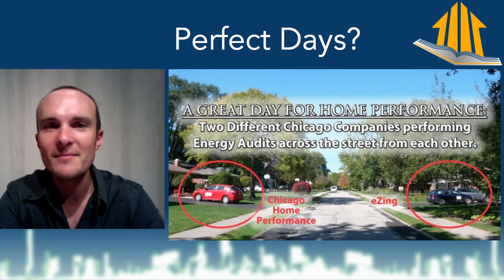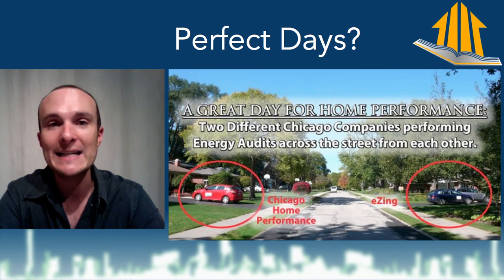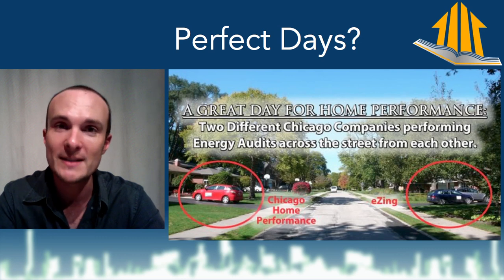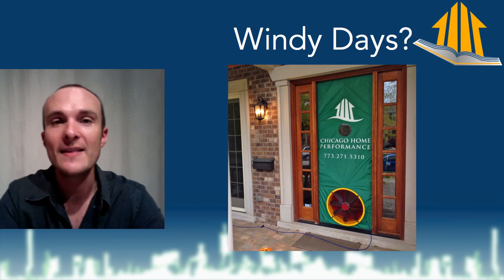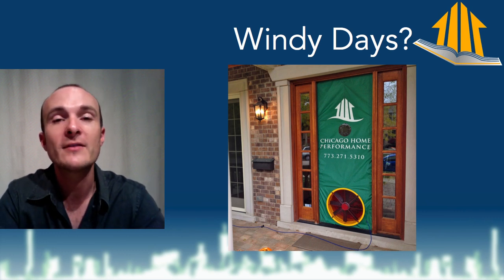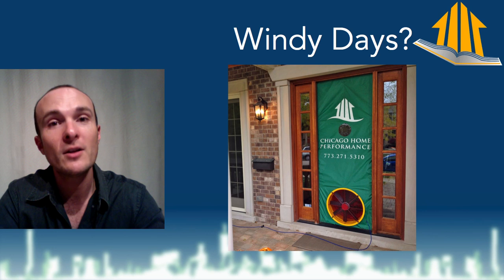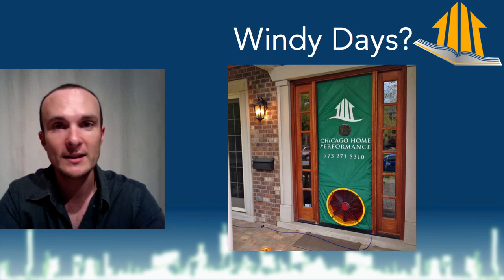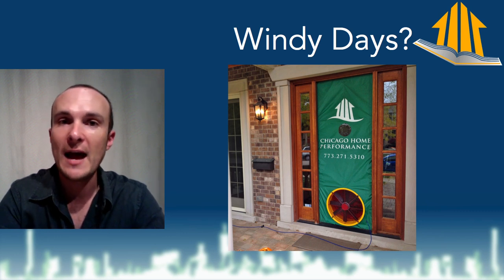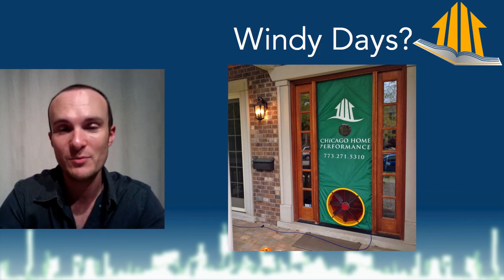None of the bits of this argument make any sense. You can do an analysis on a home or building on any type of day, as long as you have the training and the equipment, and you need to know yourself and your equipment to know when that kind of day does exist. On a windy day, this is when we get into a little bit of touchy area. The main tool in your kit is, first of all, the blower door. And the blower door is affected by wind. You're going to do something called the baseline function to account for that wind, and there are rules on how you can use the baseline and what kind of a day you would grade it based on what you find with that function.